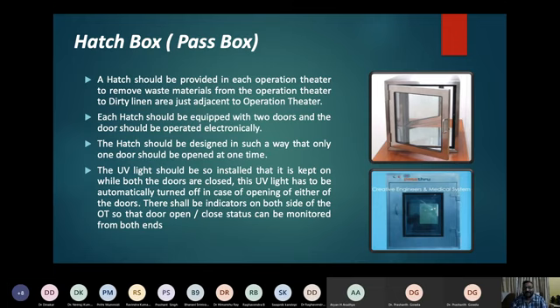So once we put the dirty linen inside and close both doors, the UV light automatically switches on, and it can kill the bacteria if available, or dilute blood stains if there. Once the UV light cuts off, the person can come through the other side and take the dirty linens or waste from the operation theater which was put inside. This is optional, but most MOT use the hatch box or pass box.